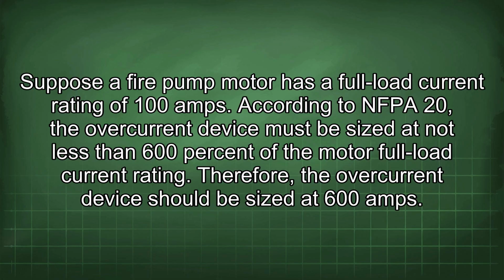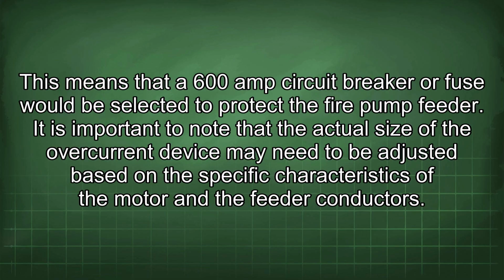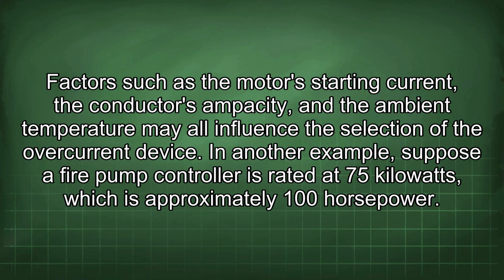Suppose a fire pump motor has a full load current rating of 100 amps. According to NFPA 20, the overcurrent device must be sized at not less than 600% of the motor full load current rating. Therefore, the overcurrent device should be sized at 600 amps. This means that a 600 amp circuit breaker or fuse would be selected to protect the fire pump feeder. It is important to note that the actual size of the overcurrent device may need to be adjusted based on the specific characteristics of the motor and the feeder conductors. Factors such as the motor's starting current, the conductor's ampacity, and the ambient temperature may all influence the selection of the overcurrent device.